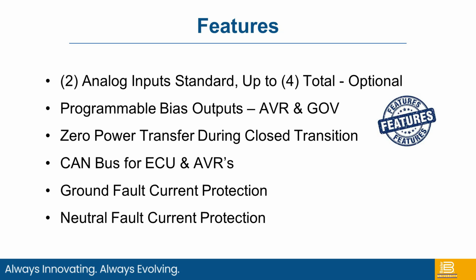So if you want to set it at 10%, just so you don't have an opportunity to go into reverse power, that's all very highly configurable. We have a wide array of CAN bus programs already set in the BestComms software for the electronic engines and AVRs. So as I had said earlier, there's programmable bias outputs. That can be a digital, it can also be analog, or it can be through a CAN bus, as long as the AVRs accept a CAN bus input. We also have a ground fault and neutral fault current protection already built in.